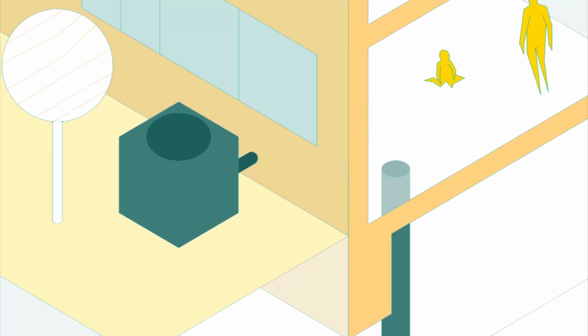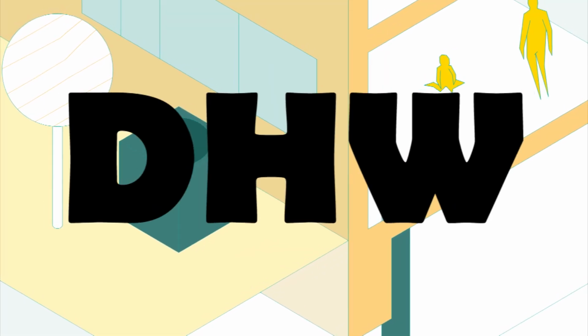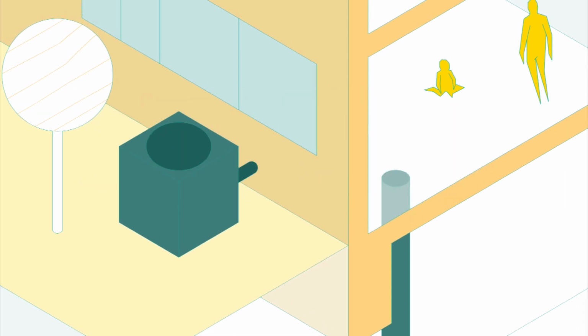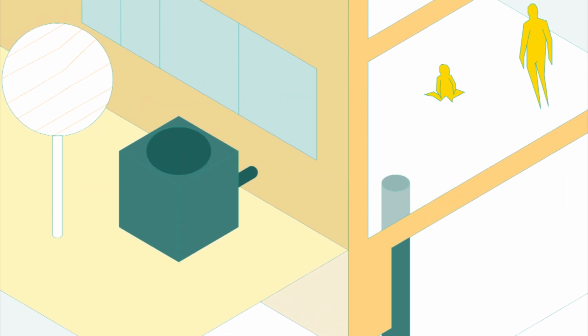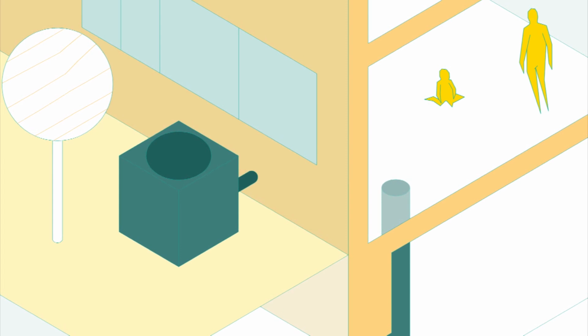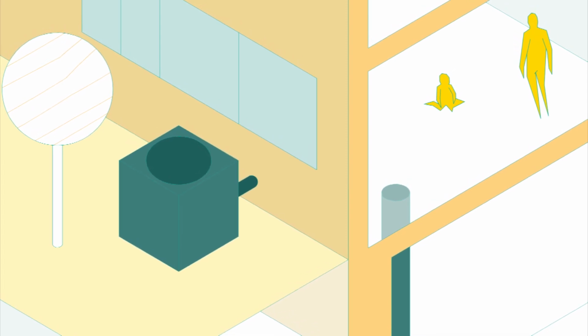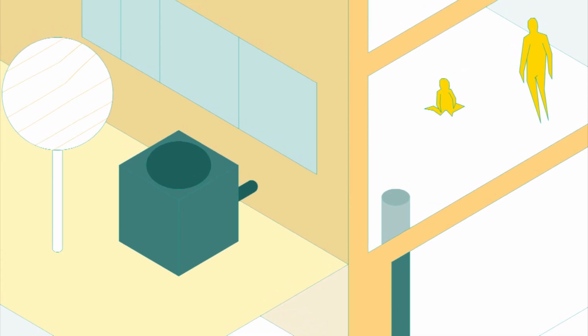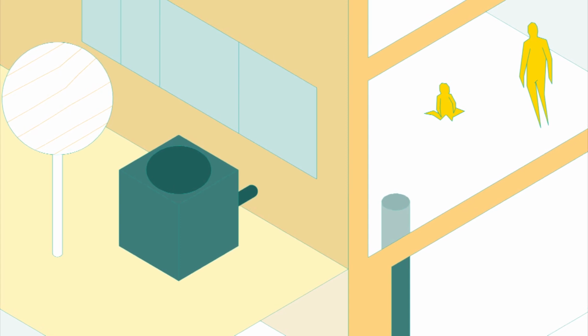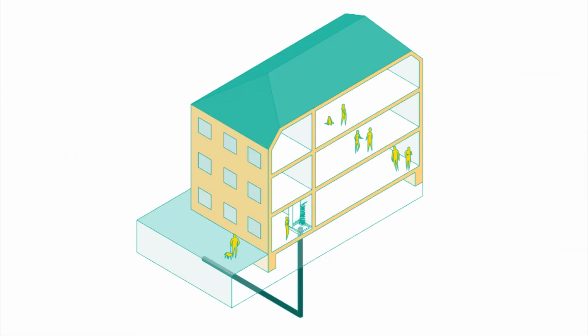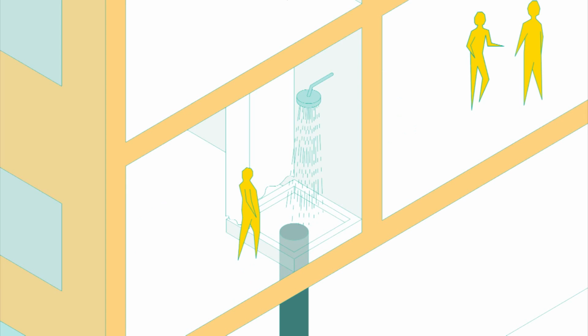A booster heat pump is used to provide the houses with domestic hot water, pumping the temperature up to 70 degrees. By increasing the temperature at the end of the line, the losses are reduced, since distribution is done at a much lower temperature. Sewers are generally at a temperature of 23 degrees. This is due to the drain of washing machines, dishwashers and showers.